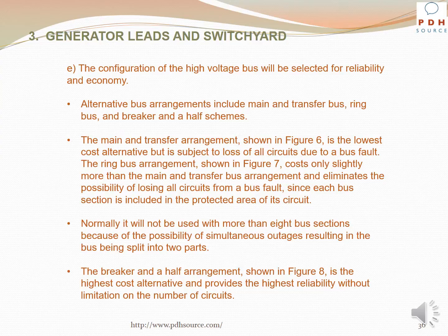The ring bus arrangement shown in Figure 7 costs only slightly more than the main and transfer bus arrangement and eliminates the possibility of losing all circuits from a bus fault, since each bus section is included in the protected area of its circuit. Normally it will not be used with more than 8 bus sections because of the possibility of simultaneous outages resulting in the bus being split into 2 parts. The breaker and a half arrangement shown in Figure 8 is the highest cost alternative and provides the highest reliability without limitation on the number of circuits.